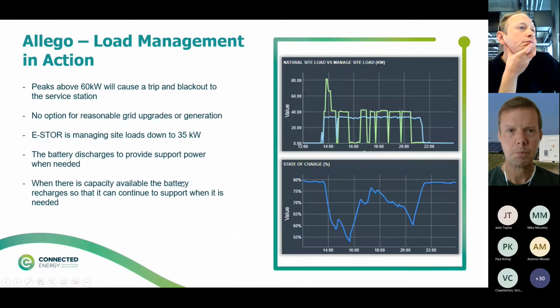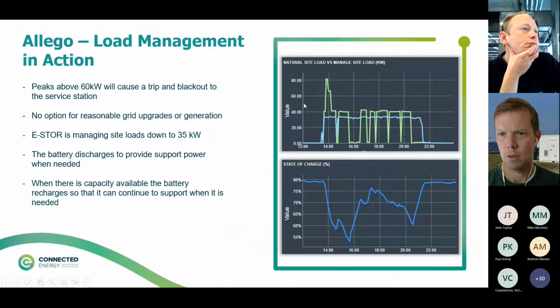And this shows what the battery storage system is doing in practice. So we're managing the site load down to 35 kilowatts. You can see here the natural load is the neon green. So they have a 60 kilowatt limit, so they would breach here, and that could trip the site.